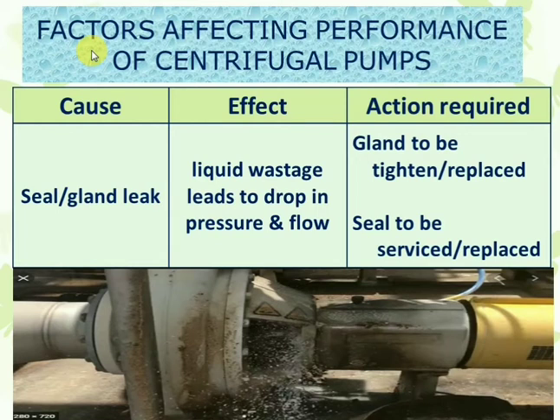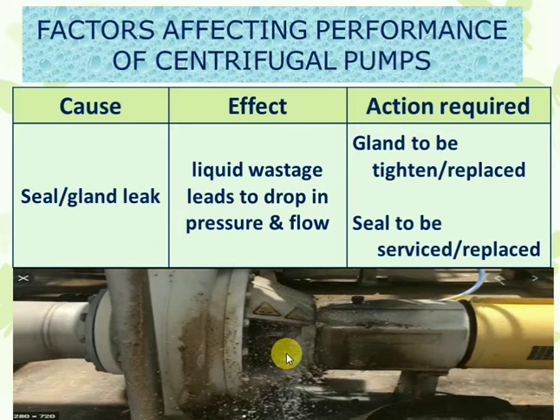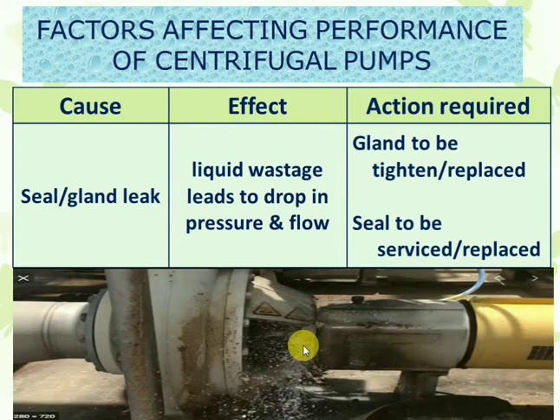In the case of a mechanical seal, leakage should be completely avoided — there should be no leak from the seal. In this picture, we can see water splashing out from the gland or mechanical seal. In the case of hazardous liquids like ammonia, carbamide solution, sulfuric acid, or hydrochloric acid, nothing should come out from any seal. We should immediately isolate the leak, stop the pump, isolate the suction and discharge valves, and drain it completely.